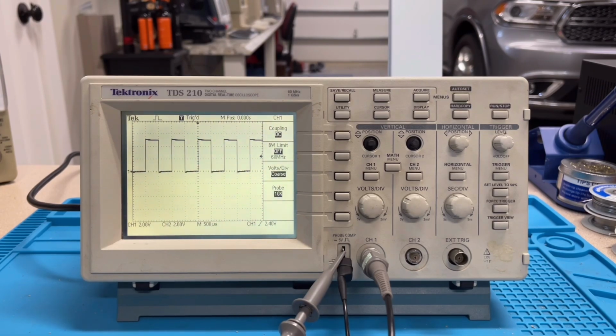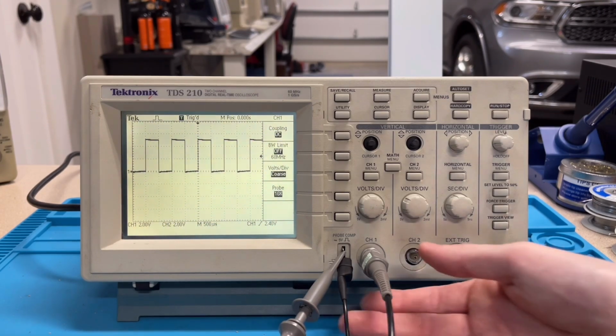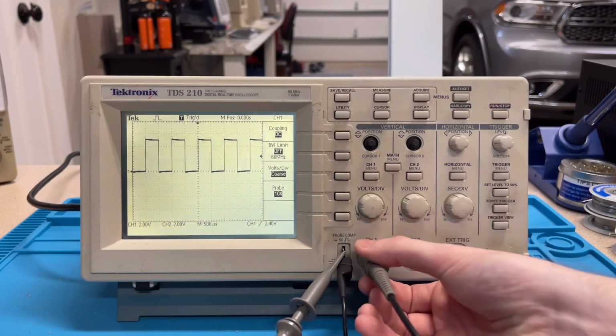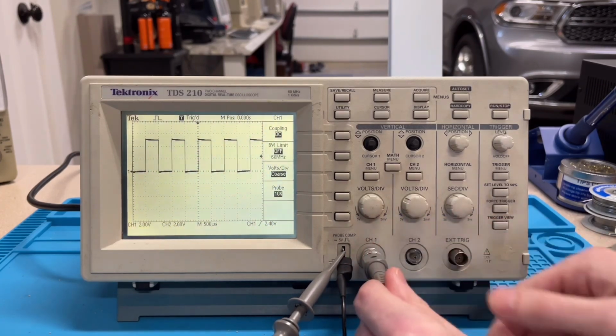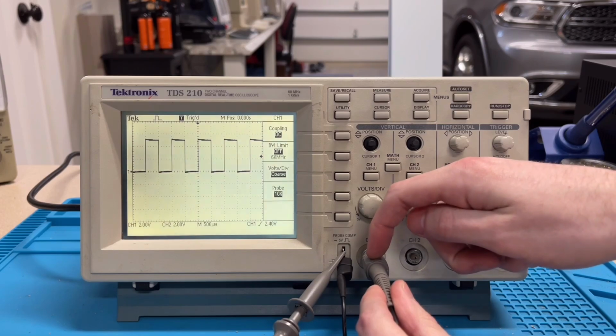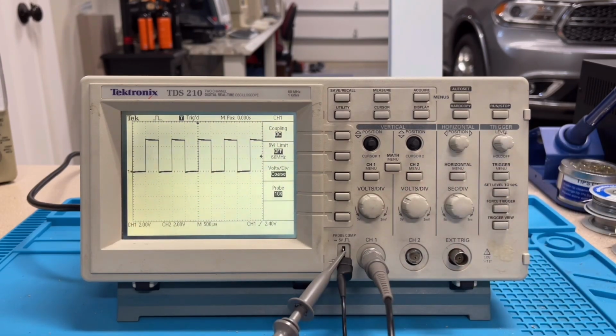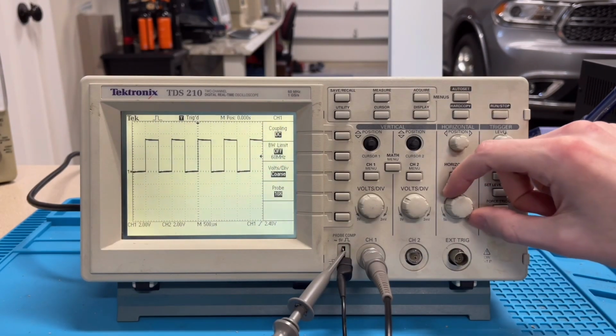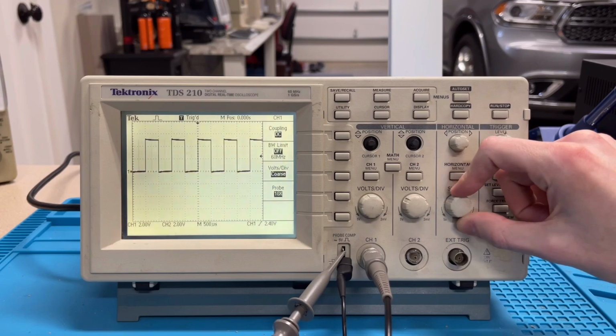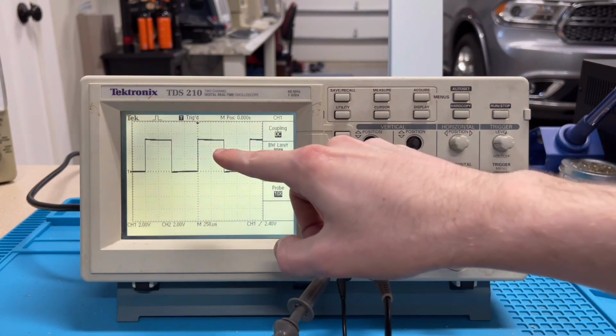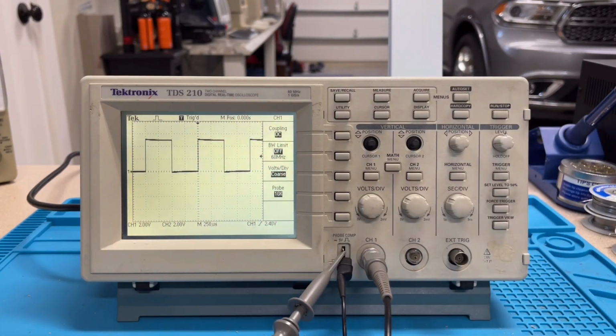But in order to calibrate the probes, there's a little adjustment on the probe. If I go ahead and turn it, you can see we have a little hole right there. There's a potentiometer in there, and you're supposed to adjust that until you get a nice flat square wave. So if I go ahead and increase my time base, you can get a better view of that. It's pretty good right now, but I'll go ahead and put an adjuster in there and show you what that looks like when you're adjusting it.